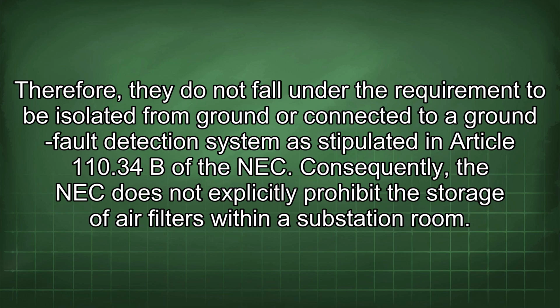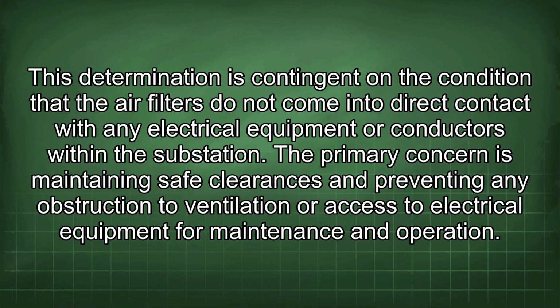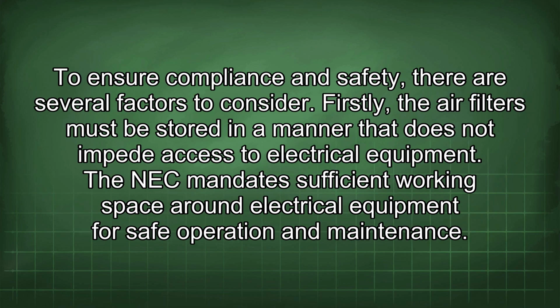Consequently, the NEC does not explicitly prohibit the storage of air filters within a substation room. This determination is contingent on the condition that the air filters do not come into direct contact with any electrical equipment or conductors within the substation. The primary concern is maintaining safe clearances and preventing any obstruction to ventilation or access to electrical equipment for maintenance and operation. To ensure compliance and safety, there are several factors to consider.